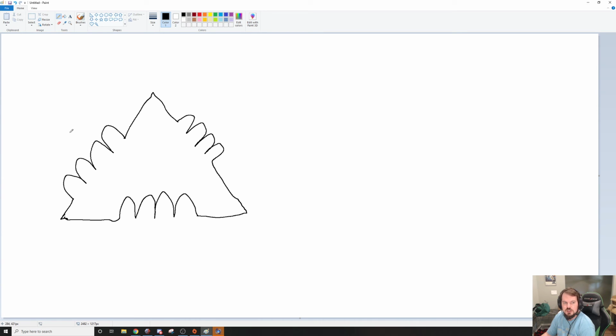So this would be transformer A, B, and C. Here is the lead. What this is doing, you take one lead from transformer A and connect it together with transformer C. Then you take the other lead from A and connect it to B. Then you take the other leads from B and C and connect them together. That's drawn out in a more schematic way.